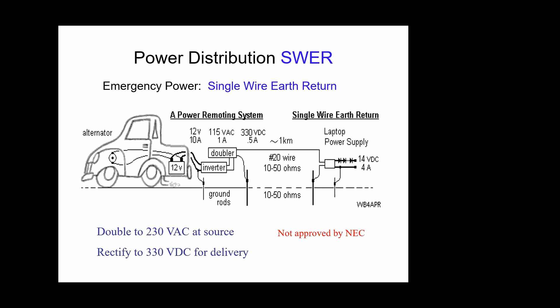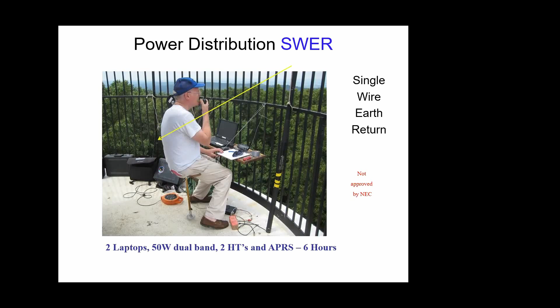This is kind of what it looks like, and there I am operating at the top. So this is just showing you a way of using emergency power. It's not legal in the United States to do single wire earth return tied to the grid, but of course this is independent of the grid. And of course I'm taking a risk of having 330 volts DC on a wire that's unprotected, but that's a risk I took for this demonstration.